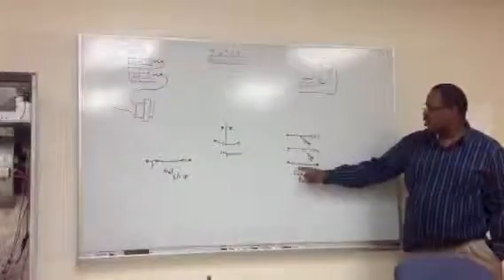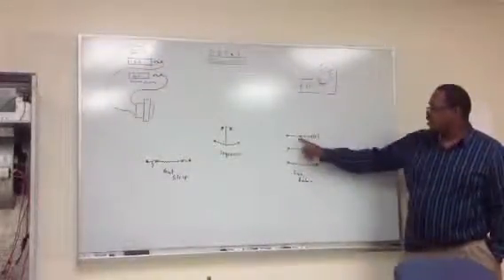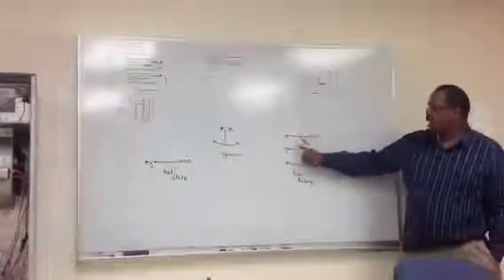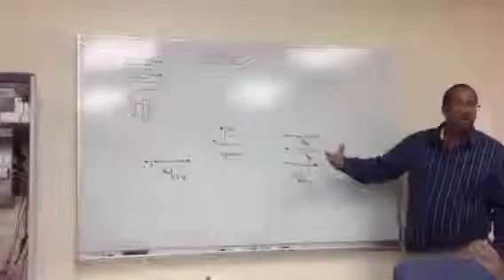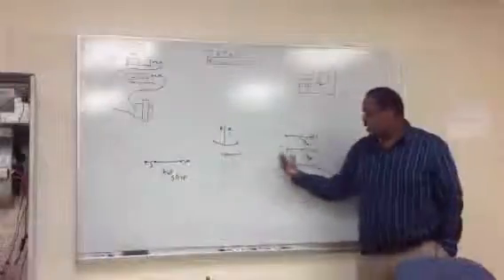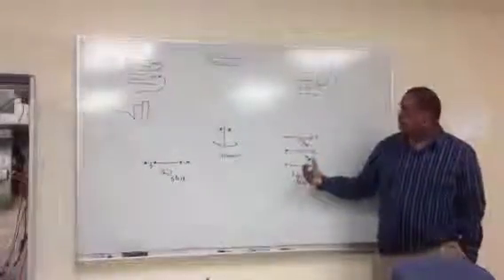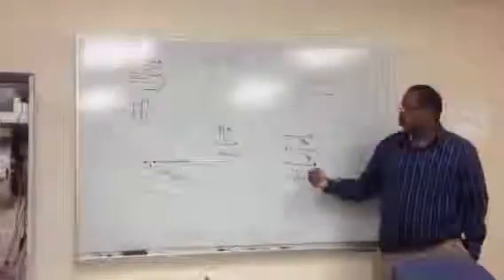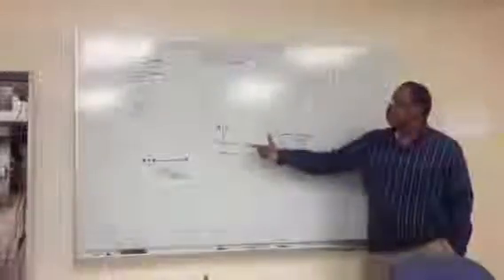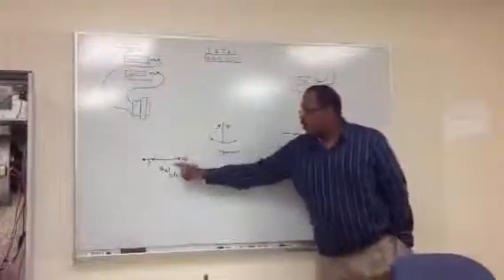We have here one circuit, two circuits, another circuit. Low voltage on the bottom, and then we use these circuits to pass power. It can pass low voltage and it can pass high voltage, but for the most part, it will be controlling high voltage. So we call our fan relay and our sequencer our low voltage controls, or our low voltage loads. But in high voltage, we call our sequencer and our fan relay switches. Yes, there are switches for our high voltage because they control high voltage loads, the heat strip and the fan.